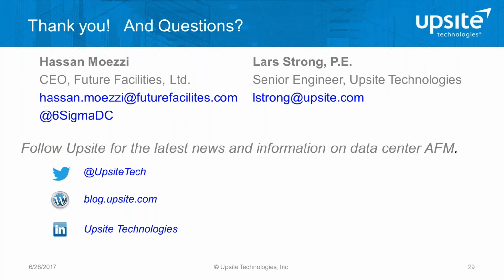This comes up with containment, and as the person asking noted, what about economization? It comes down to the ratio of supplied air to IT demand air—IT equipment has varying airflow demands, spinning up and requiring more cooling at some times than others. Without sophisticated monitoring and controls, you simply have to throw more air at it all the time than it needs, meeting its highest demand, and at other times you're wasting energy and being inefficient.